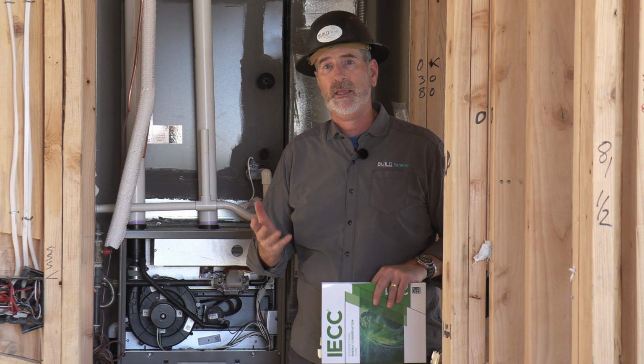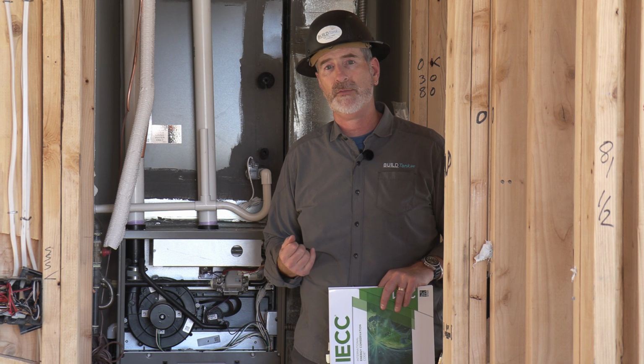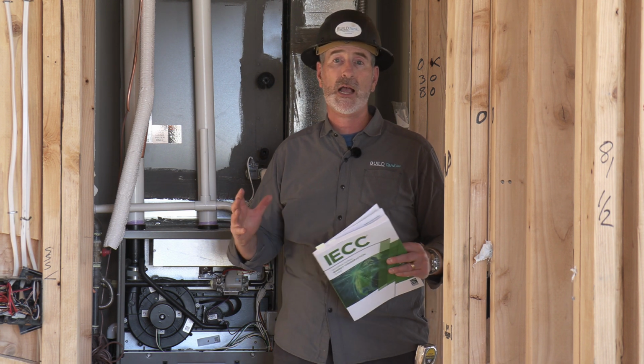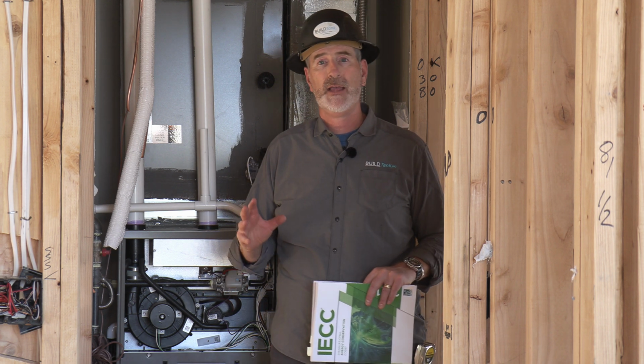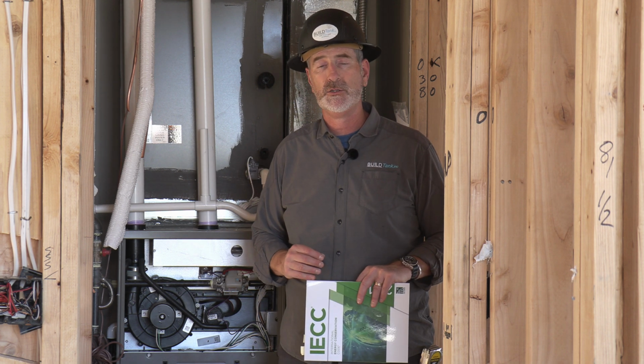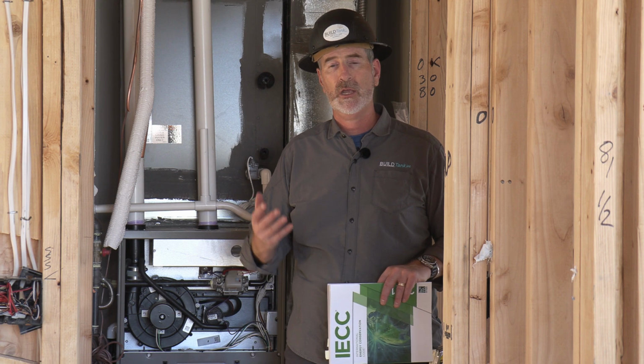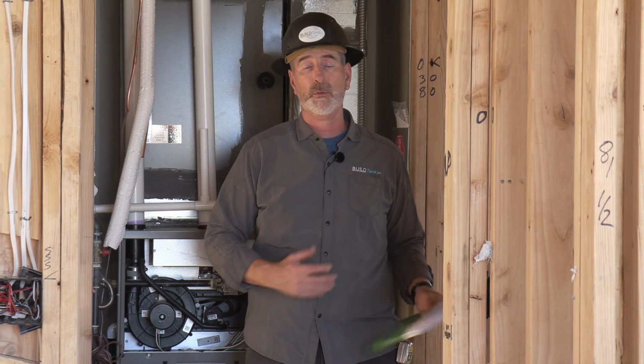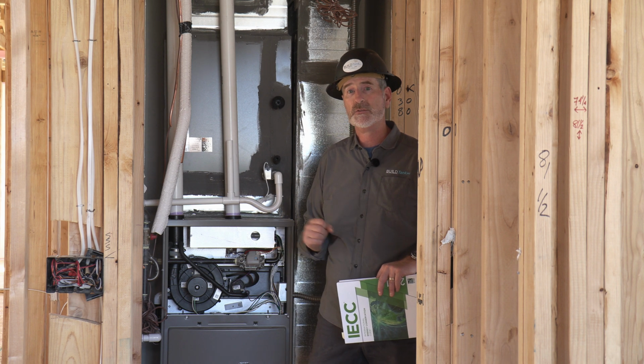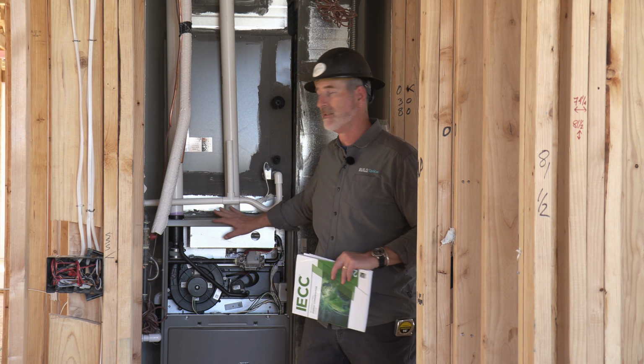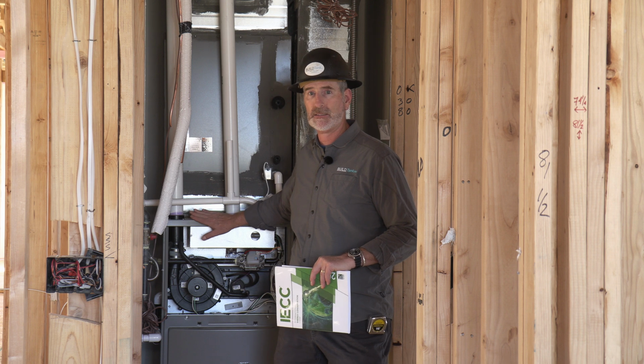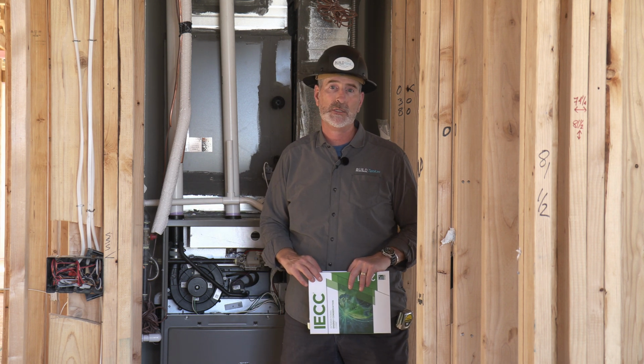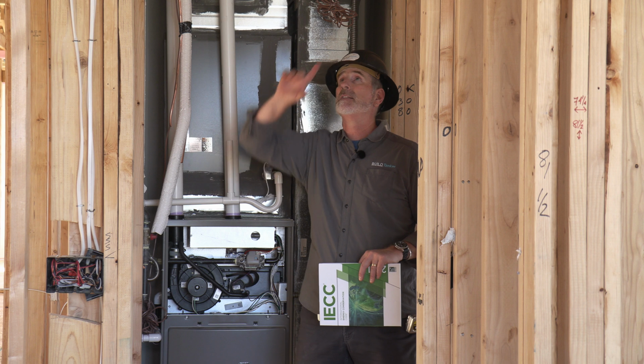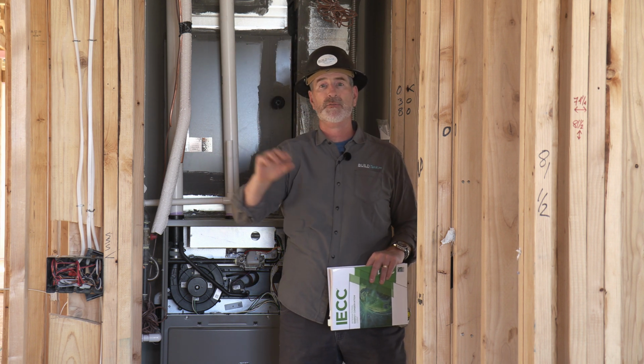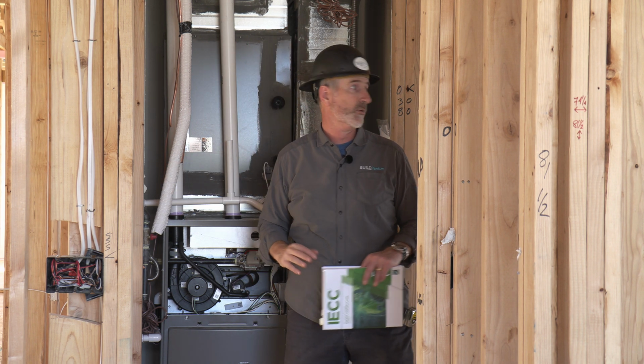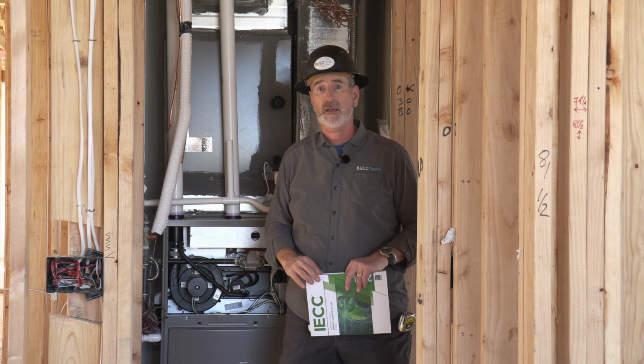So the Manual J is doing a heating and cooling load on the house. In order to size this system, we have to have that load. We need to know how many BTUs we need to heat and cool the house on the coldest day of the year and on the warmest day of the year. Then we use Manual S to size the system to have the proper capacity to meet those heating and cooling loads. And then we use Manual D to design the duct system to be able to deliver the load into each bedroom or living space in the house here.